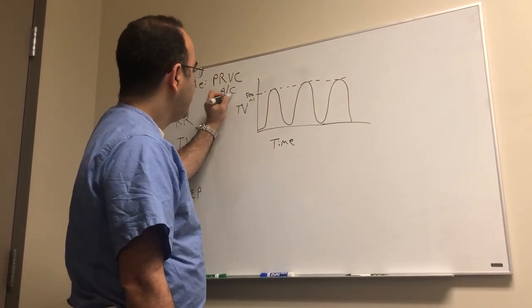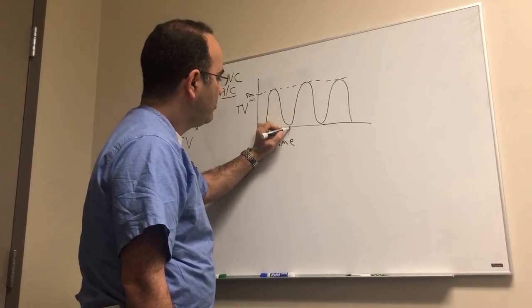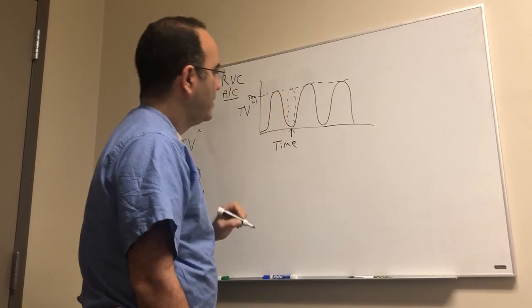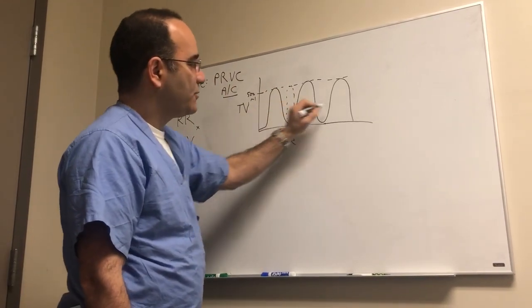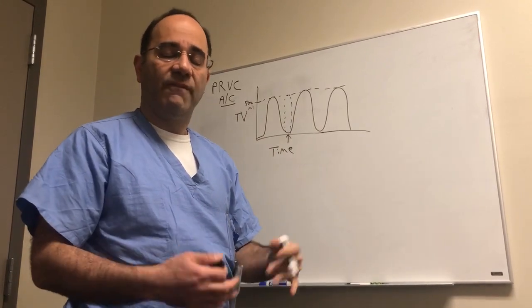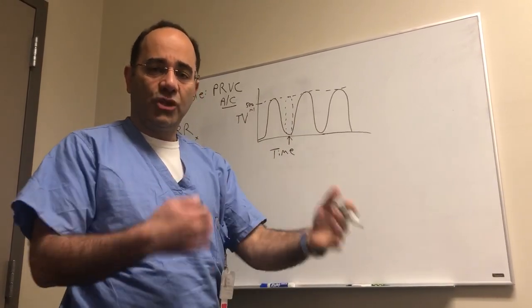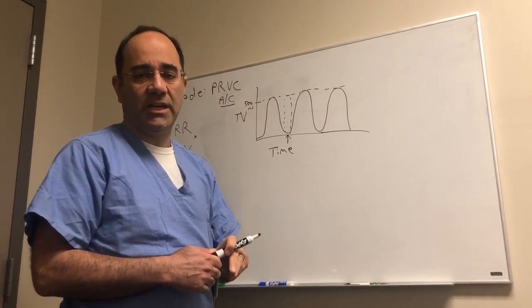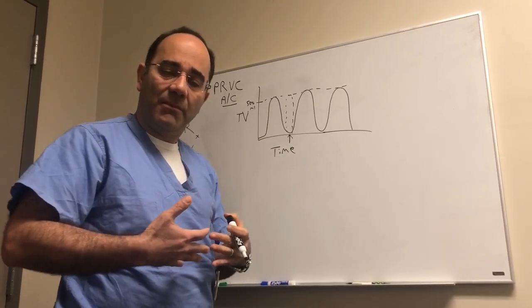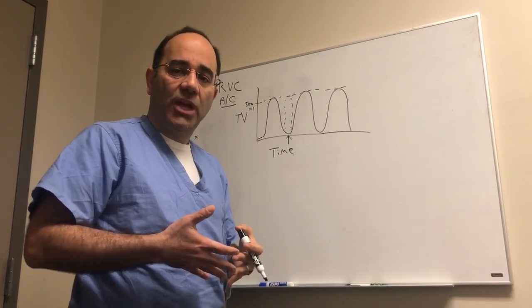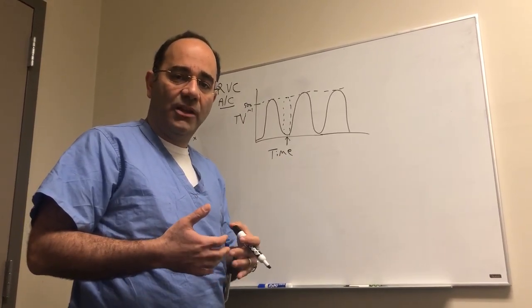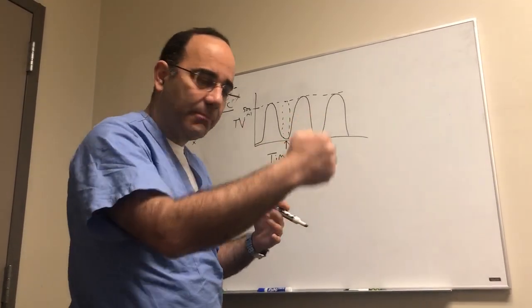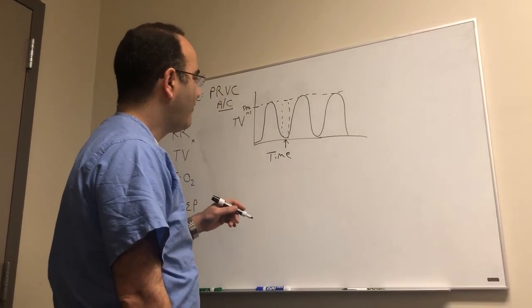In a PRVC mode or an assist control mode, if the person decides to breathe right there, he or she will get a fully supported breath. So yes, you dialed in a respiratory rate of 10. The patient decided he wants to breathe 14 times per minute. Those additional four breaths will receive 500 milliliters of air with very little effort. All the person has to do is contract their diaphragm a little bit. The machine will sense a negative change in the airway pressure and in doing so, it'll go ahead and deliver 500 milliliters of air almost like a piston being pushed into the mouth. No effort required for the patient.